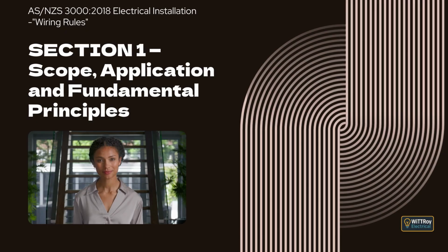Clause 1.4.82 is main switch. This is a switch whose primary function is to isolate the electrical installation from the supply. It may also meet regulatory requirements if it is labeled properly. Clause 1.4.83 is multiple earthed neutral, also called MEN system. This is an earthing system where parts of an installation that need to be earthed are connected to the general mass of earth and also connected to the neutral conductor of the supply or the PEN conductor. Within the installation, the protective earthing conductor is separated from the neutral conductor.